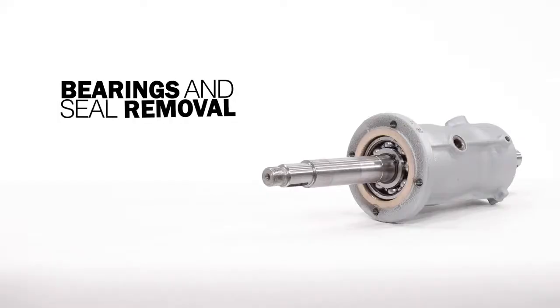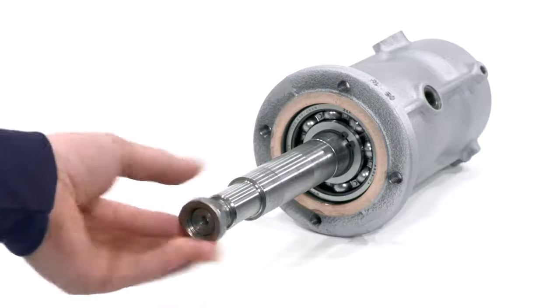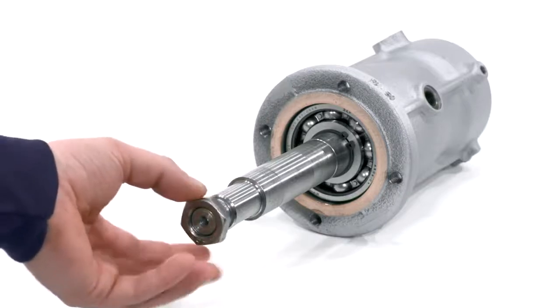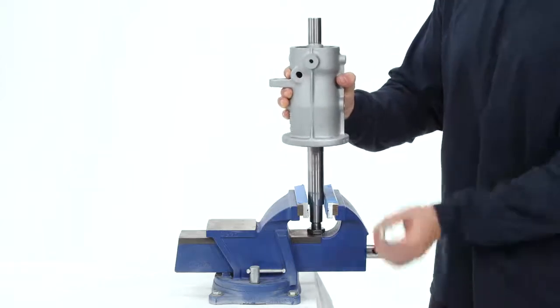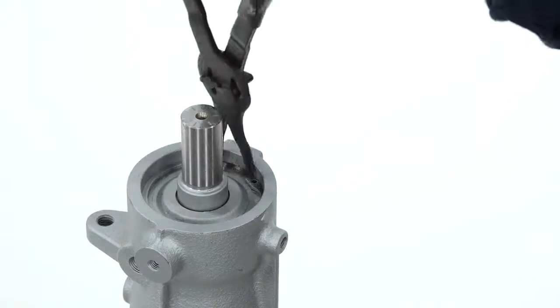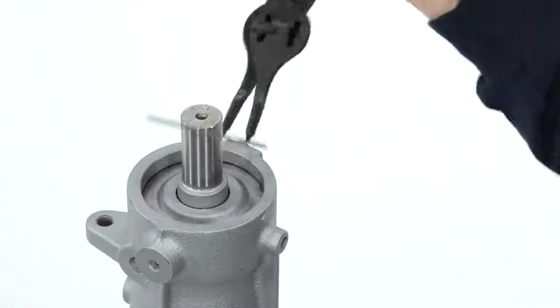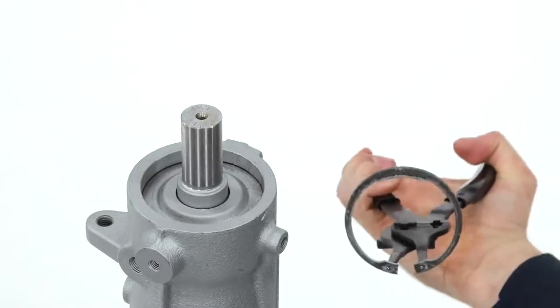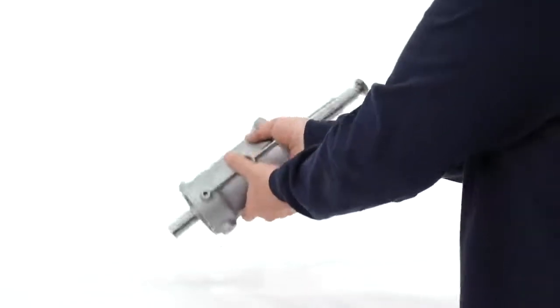Bearings and seal removal: You may wish to add the nut back onto the shaft to protect the threads. Place the shaft and bearing housing vertically in a vise, thread side down. Remove the outer snap ring from the pump drive shaft at the bearing. Flip the housing to remove the Nilos ring and spring disc.